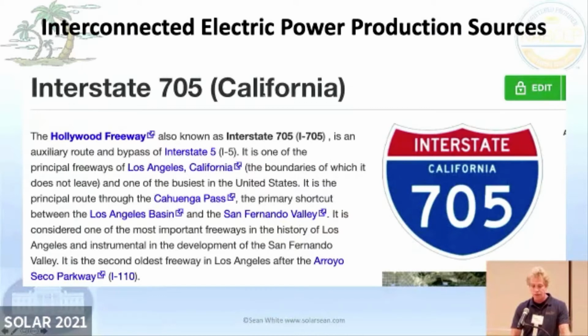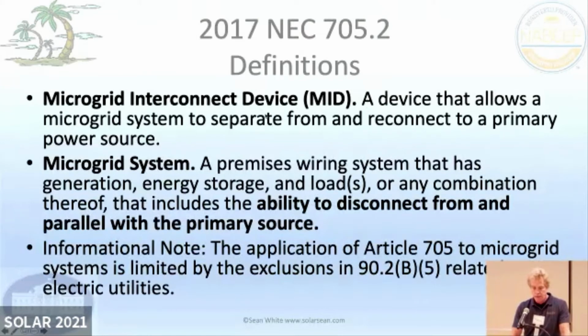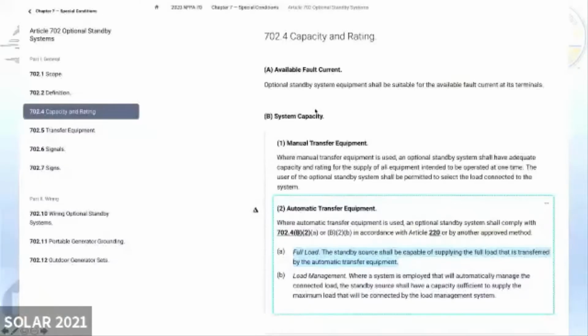So this is our transition in between here. And it is Article 705. If you're from Southern California, you've got to remember that because you're on the freeway. And so we think of this as interconnections mostly. Like we talk about how we're going to connect to the grid. We've got currents coming from two different directions. So connecting to the grid would be load side connections. You've heard of the 120% rule, maybe. And supply side connections, a lot of you have heard of that before. Now what we're looking at is something called a microgrid interconnect device. And let me just skip ahead here.